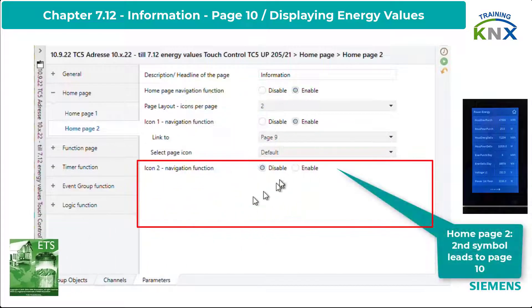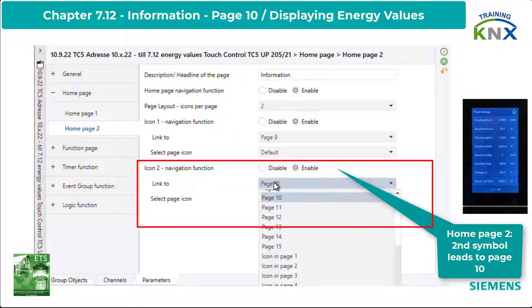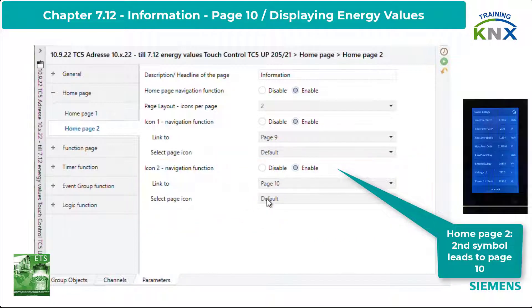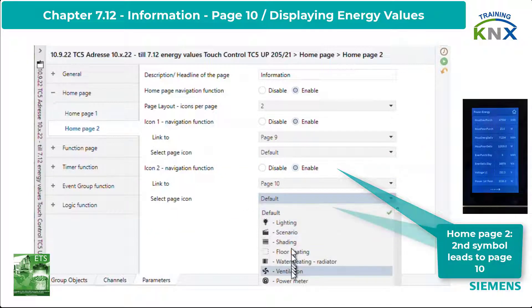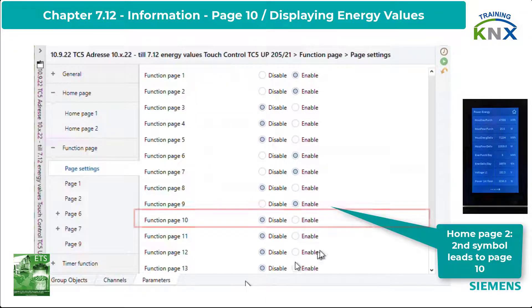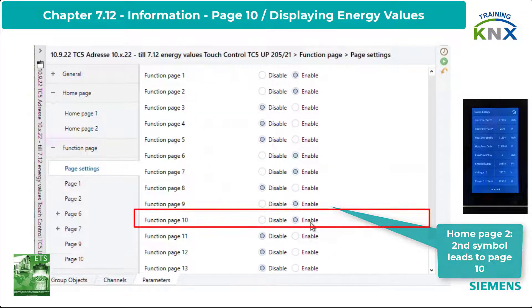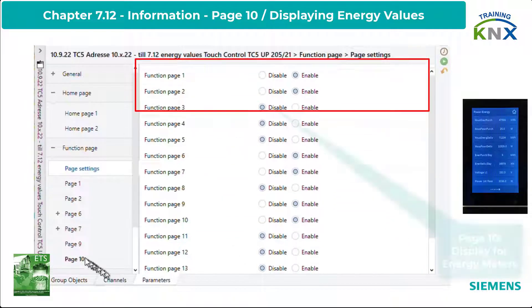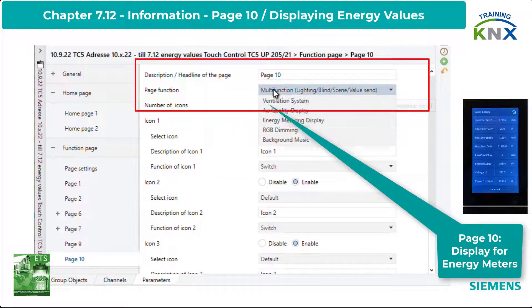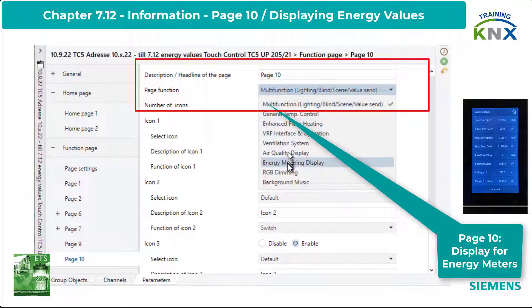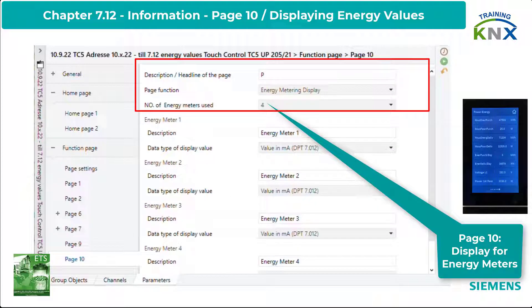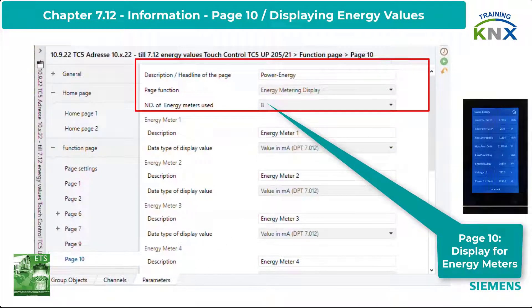I now extend home page 2 by function page 10. I select Power Meter. In the function pages, I release page 10 and set the function Energy Metering Display. To cope with the 15-letter limit, my page heading is 'Power Energy'. I set the maximum of 8 displays.